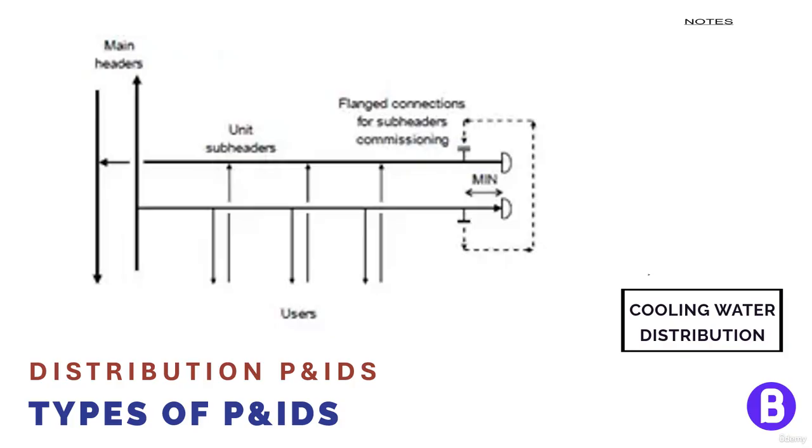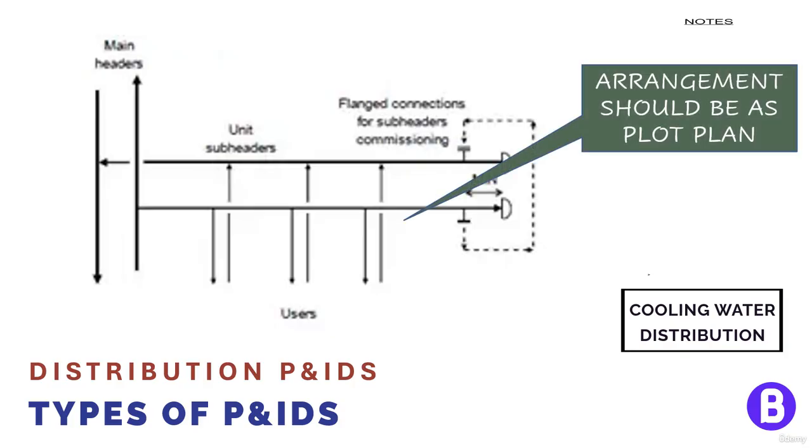In these P&IDs, utility users or effluent sources are laid out geographically to preserve all elements, sequencing, and relative locations. So let's take the cooling water supply as an example. We have multiple water coolers across the plant, so we need to show how the cooling water header adjusts the distribution of the cooling water lines. This makes it easier to predict the system hydraulics.